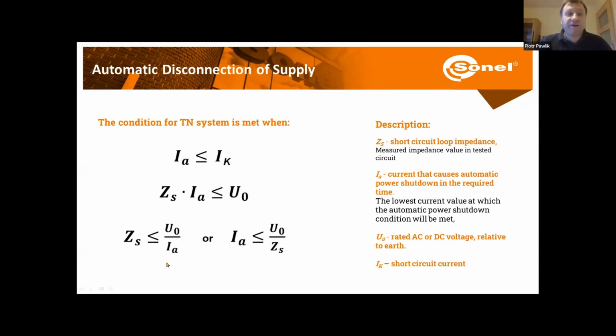So obviously we cannot measure fault current, it has to be calculated. So we can measure the supply voltage, we can measure fault loop impedance, and the calculation of the two will give us the value of fault current.